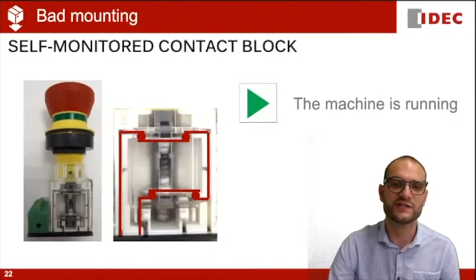If the e-stop is correctly mounted, the machine is running. If the button is pressed, the first contact, normally closed contact, opens and stops the machine. If the operator is removed or if the contact block has not been properly attached, the second contact, the normally open contact, will open and keep the machine on a safe state.